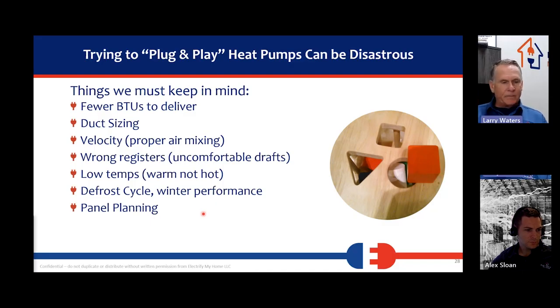In my house, I had a 50 amp breaker going to a 4-ton unit on the outside of my house. My new heat pump only needs a 20 amp breaker. I was able to free up capacity to do other things in my house because my new system used so much less energy. And it's the type of system where the outdoor unit actually powers the indoor. So I'm powering the indoor and the outdoor for 20 amps, where just my old outdoor unit had a 50 amp breaker. So panel planning is extremely important because these customers are going to have to get other things taken care of as they electrify their houses.